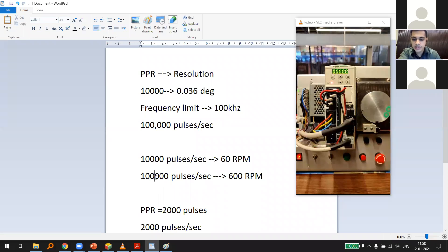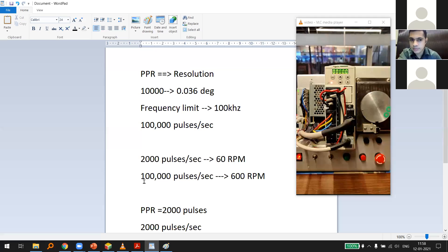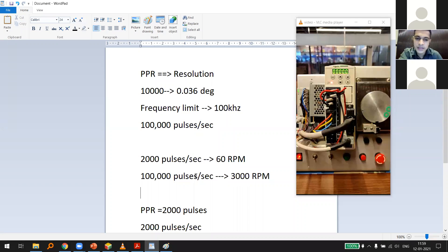With 2,000 PPR: 2,000 pulses per second gives 60 RPM, and 100,000 pulses per second gives 3,000 RPM — exactly the motor's rated speed. So at 2,000 PPR, the controller's 100 kHz limit perfectly matches the motor's 3,000 RPM rating. It is a trade-off between accuracy (resolution) and achieving desired speed.